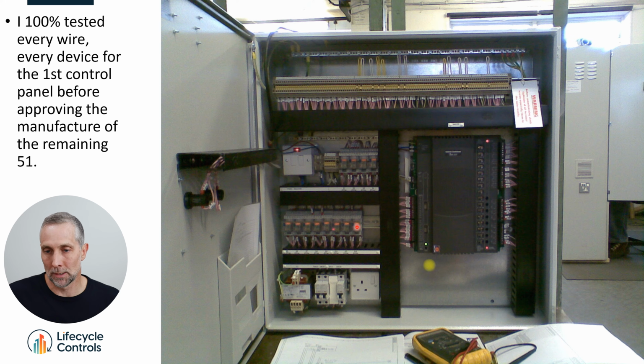This little space over here was left because the operating theater had duty standby supply and return fans with humidity controls, and I couldn't fit all the points on here. I didn't want to have an expansion module for nothing on so many AHUs. So for the operating theaters, the installers would just put 1 expansion module on here for the humidity controls and the extra fans. But basically this one panel does everything.